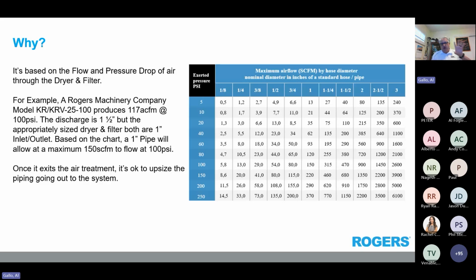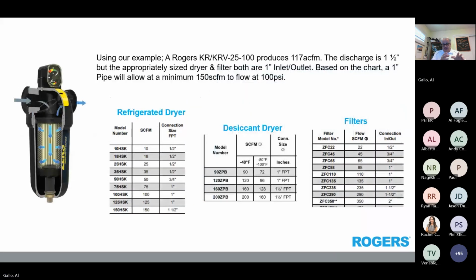So for example, and I want you to remember this example in this chart. For example, Rogers machinery, a KR or KRV 25100 generates about 117 CFM at 100 PSI. The discharge on that unit is 1.5 inches. But if we look at the dryer, and it's on the very next slide, it's actually rated only 1 inch. Going into the refrigerated dryer, it's 1 inch. Going in the desiccant dryer, it's 1 inch. And also the filters, it's all 1 inch.